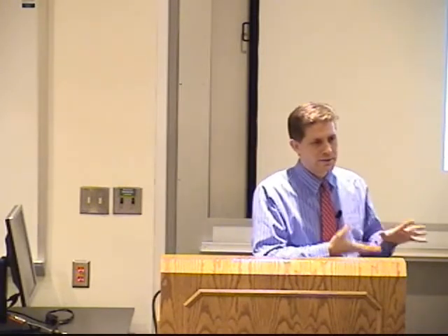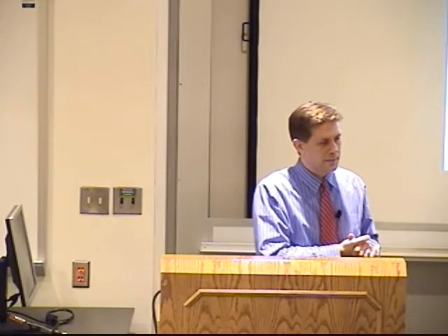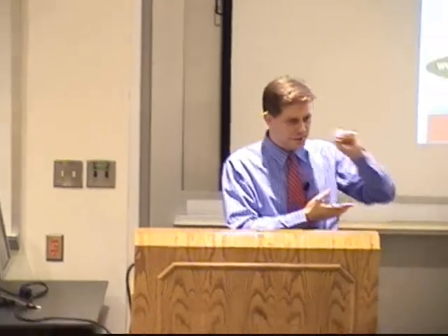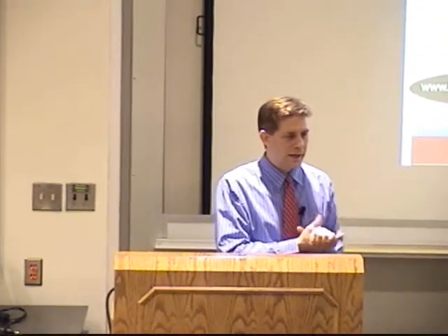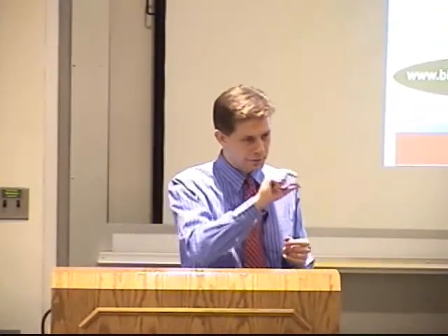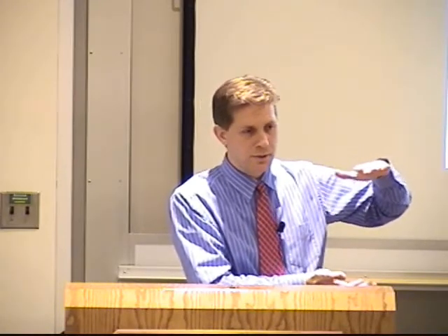Yeah, so what ISAM does is it eliminates a lot of the mechanical scanning that we would necessarily have to do. You can imagine if we take a cross-sectional image, there is a focal point within that image, and as we go for higher and higher resolution, that focal region gets smaller. And so that means there's a lot more that's out of focus that traditionally people have just thrown away because it's blurred. So what ISAM does is we can capture an image at one plane, and ISAM will then allow us to make that entire illuminated plane in focus and usable. So we don't have to have the mechanics or repeat our scans at each micron depth to get that volume.